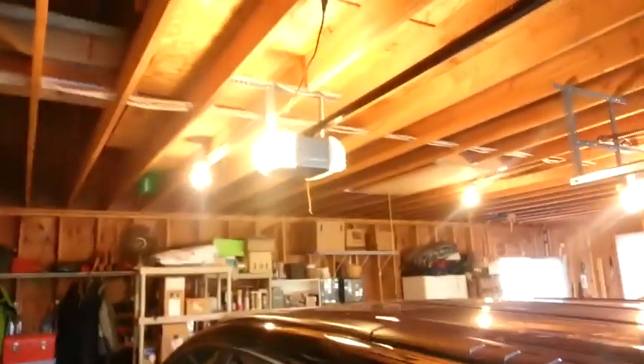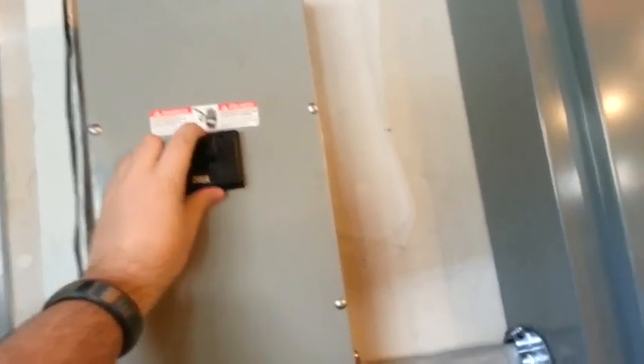So I guess this is a better time to test. So here we go. The garage opener lights will stay on, but the lights behind them will turn off, and utility room lights will also turn off for 10 seconds. And then all of a sudden you'll hear the generator kick in and we'll have power again. So here goes nothing. All off. Generator kicking in. And we'll hear a big bang from the ATS.